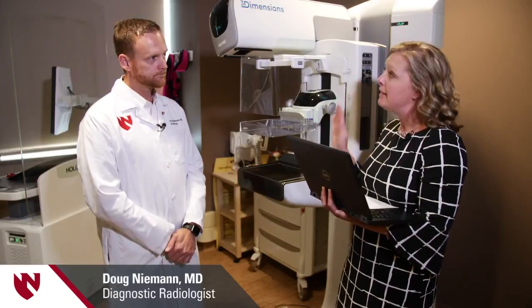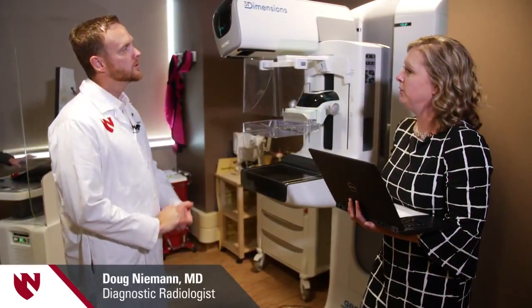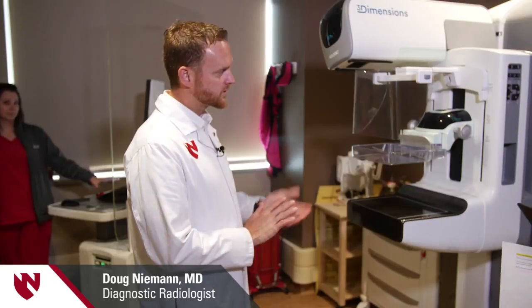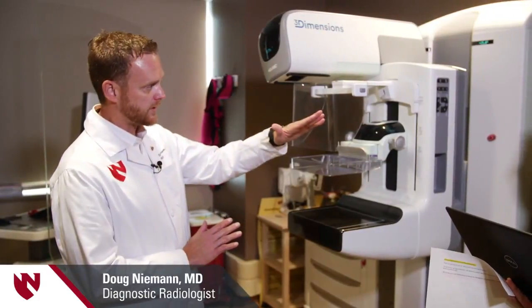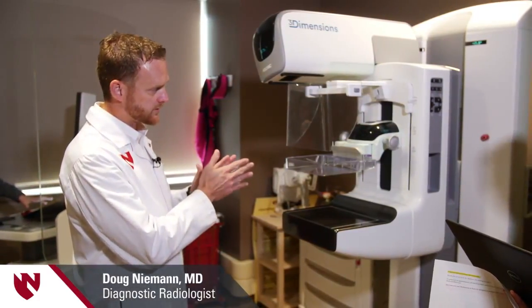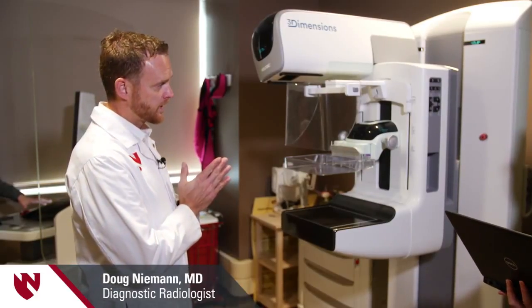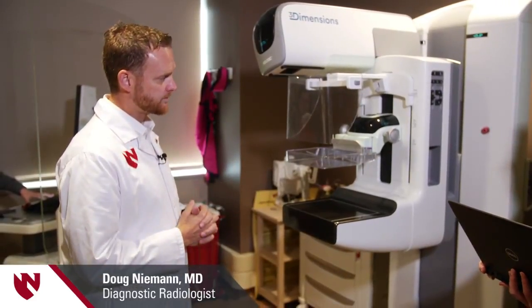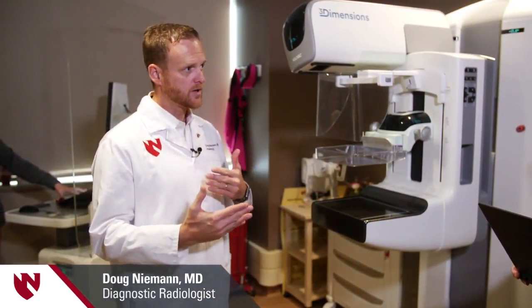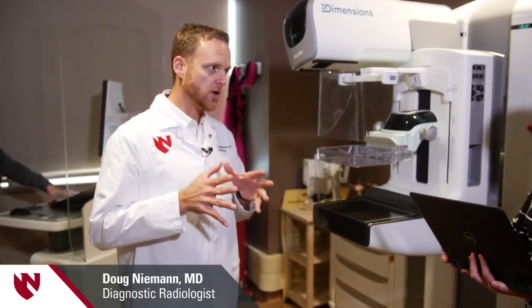We're going to have a limited example of what this is — I actually stood here the other day. So explain what the machine will do. This is the newest technology when it comes to breast imaging — this is the 3D mammogram. The machine will actually move in an arc from 15 degrees to the left to 15 degrees to the right. That creates multiple images through the breast, giving you a 3D picture versus old-fashioned 2D mammography, which gave just two images and caused summation artifact — breast tissue on breast tissue — making it harder to see through the breast.